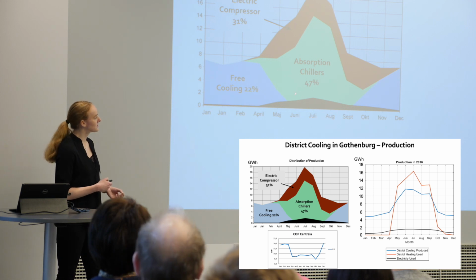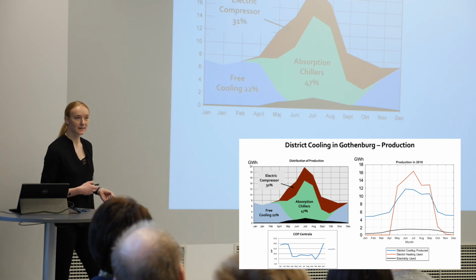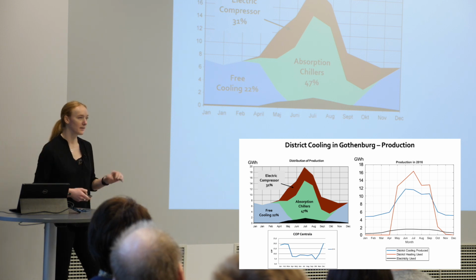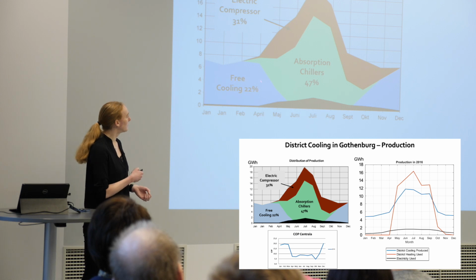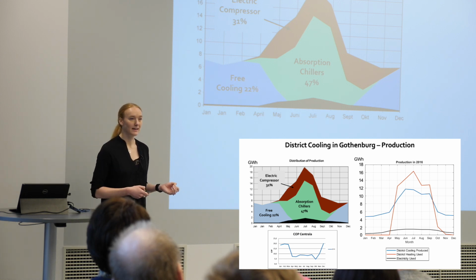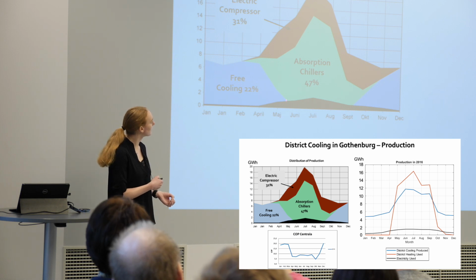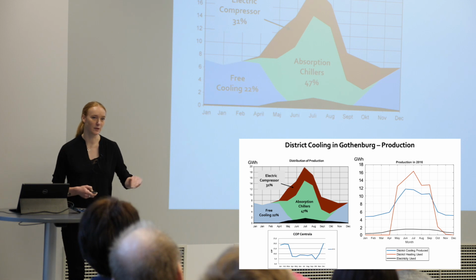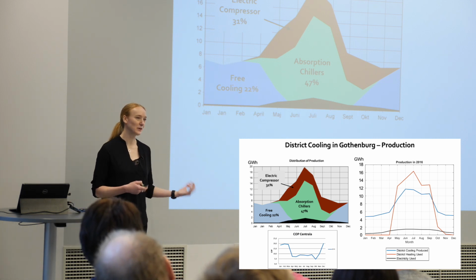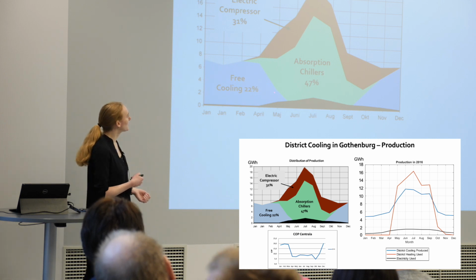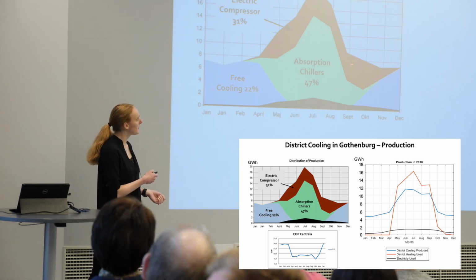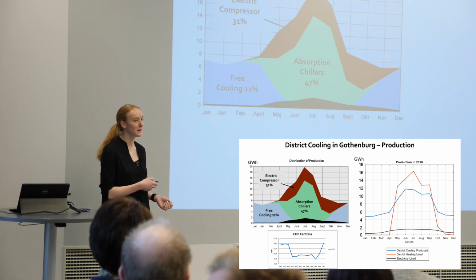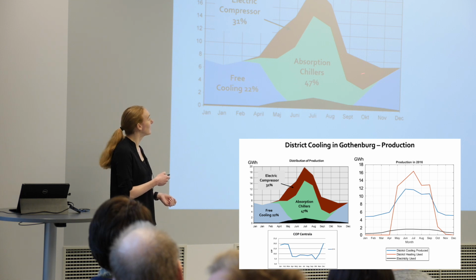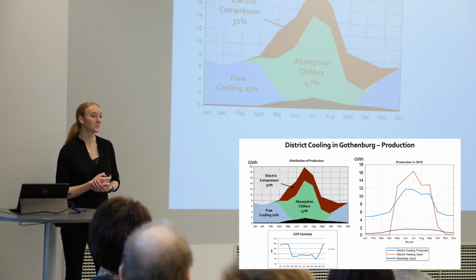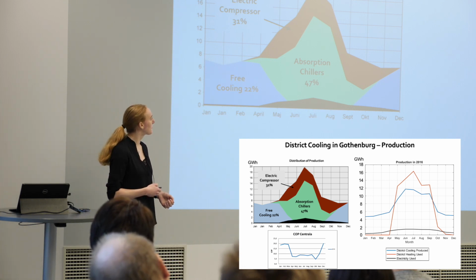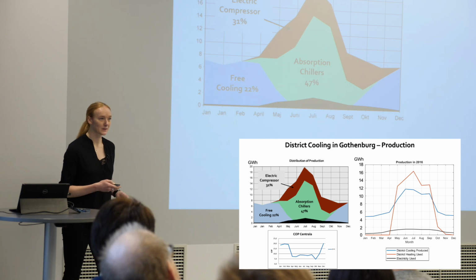And then the absorption chillers are the main supplier of cooling in the district cooling system in Gothenburg. Their share is about 47%, and they're started up when the heat demand has dropped. It varies a little bit, but usually it's around May, when the heat demand is low enough and the heat is available at zero cost for the absorption chillers. And then for peak production, and also here in the fall, when the heat is mainly used in the district heating system, the electric compressor chillers are run to produce the cooling. But the absorption chillers are the main supplier of district cooling.